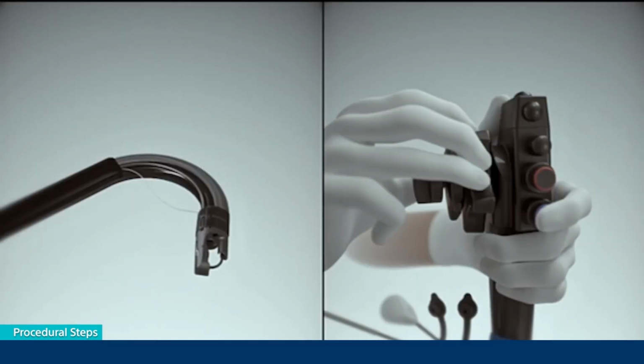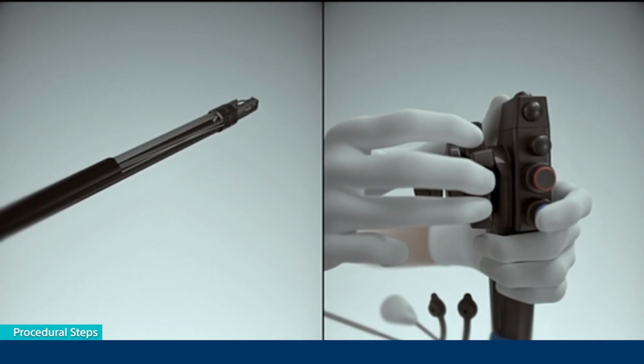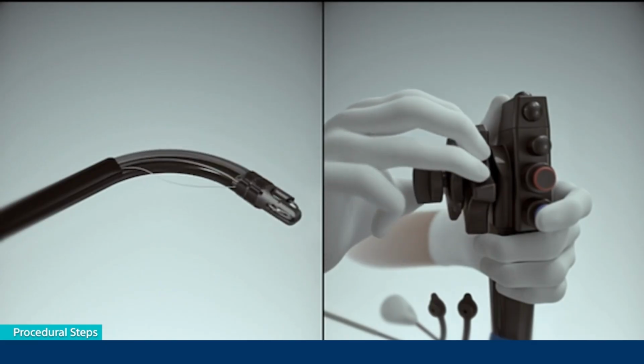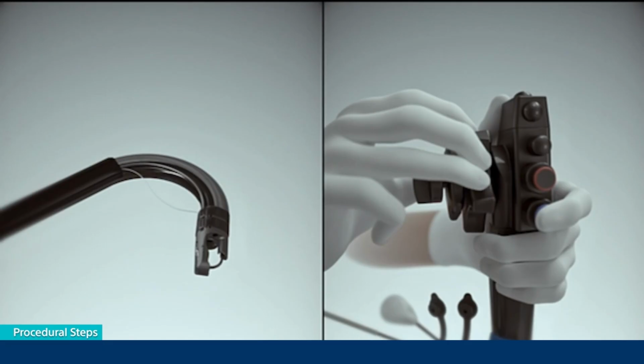MaxFlex Advanced Retroflexion should only be used on Olympus and Fuji compatible scopes with Endcap mounted as instructed to ensure added articulation is only in the scope's primary up direction. Step 1. To do this, you would need to fully articulate the scope using primary up dial and hold dial to maintain this position. Do not lock the scope wheel.